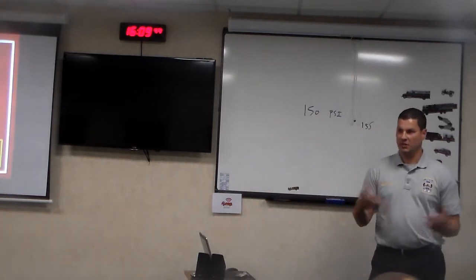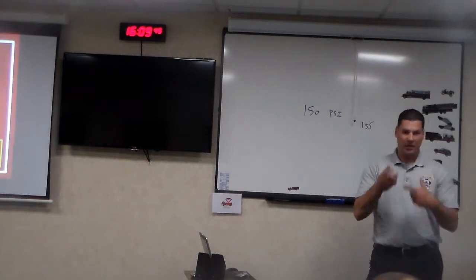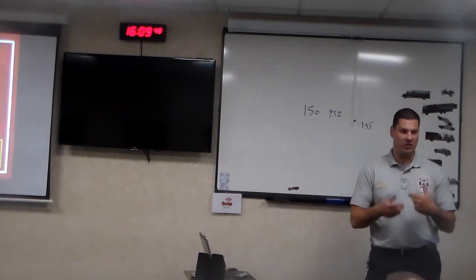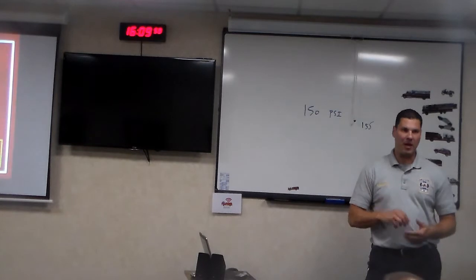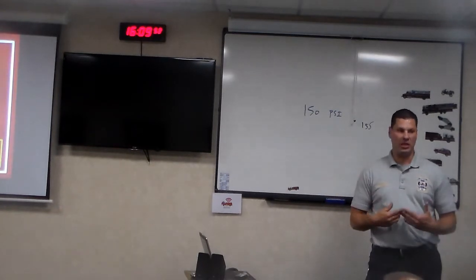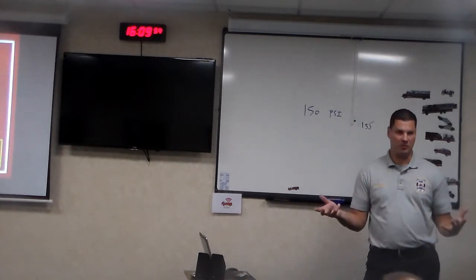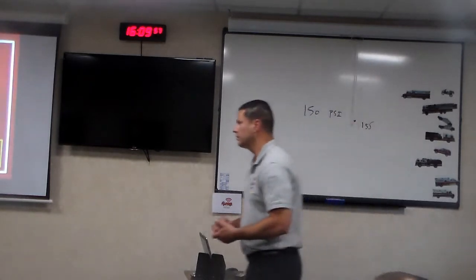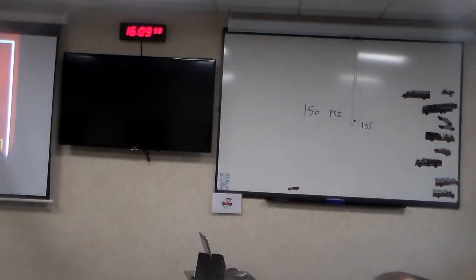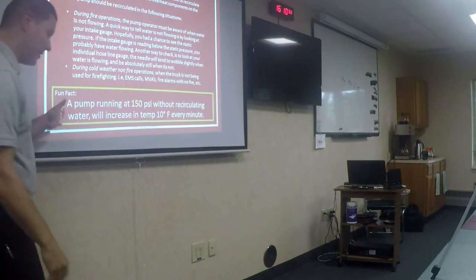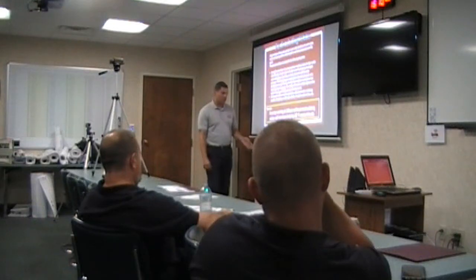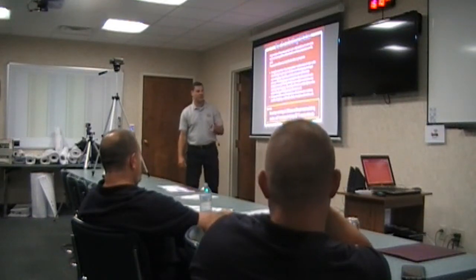So the tank water, at some point, that tank water is going to get hot too, depending on how high you have the throttle going. So at some point, you're going to need to get cold water in there in order to prevent the pump from overheating. So during fire operations, we're going to make sure that we're monitoring the temperature. Here's a fun fact I found and wanted to share: a pump running at 150 PSI without recirculating water will increase in temperature 10 degrees for every minute.